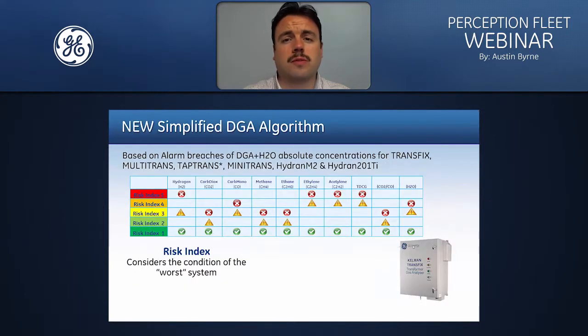One of our new algorithms that we've introduced with our latest version is the new Simplified DGA Algorithm, and it works on the alarms that are set within the online monitor and not information taken from standards and best practices. You can see in this table exactly how we look at the measurements and the alarms within the particular device. For example, hydrogen, risk index 5 is the high or alert alarm that's set in the device. Risk index of 3 is the warning, caution or high alarm that is set in the unit, and then a risk index of 1 indicates the asset is not in any alarm state.